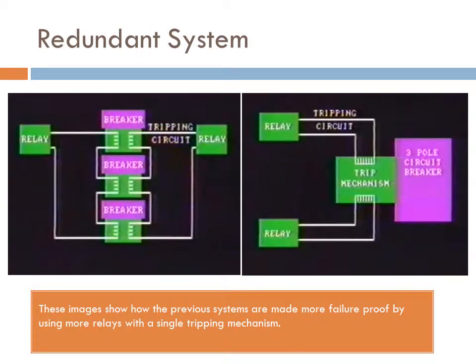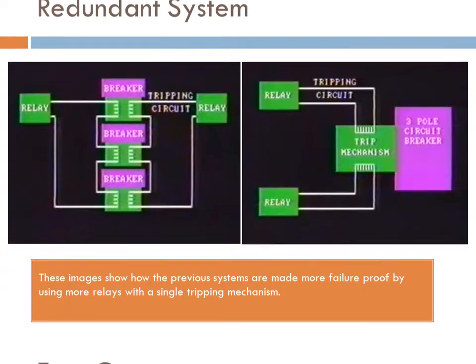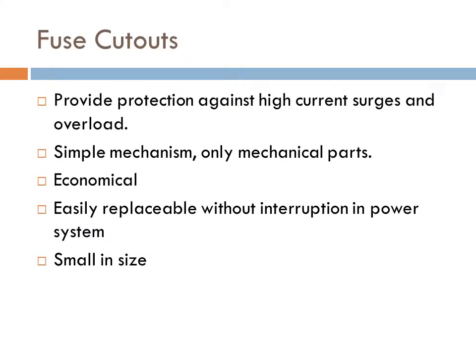It is the improved form of above circuit in which if the first relay does not work, then second is used, which can protect the system from severe damage. Fuse cutouts are mounted on poles and protect against overcurrent and short circuit fault. They are much smaller and economical than circuit breakers.